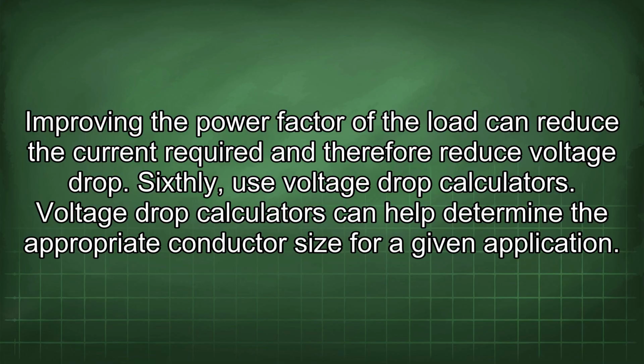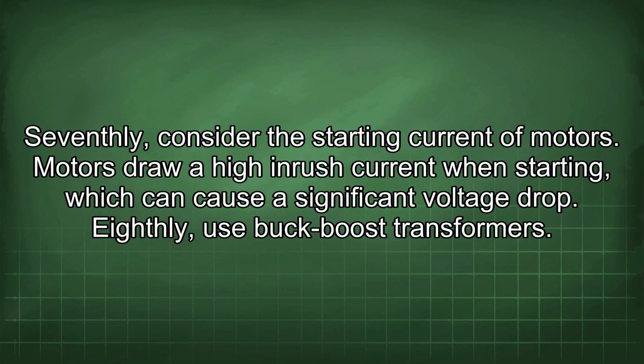Sixthly, use voltage drop calculators. Voltage drop calculators can help determine the appropriate conductor size for a given application. Seventhly, consider the starting current of motors. Motors draw a high inrush current when starting, which can cause a significant voltage drop.